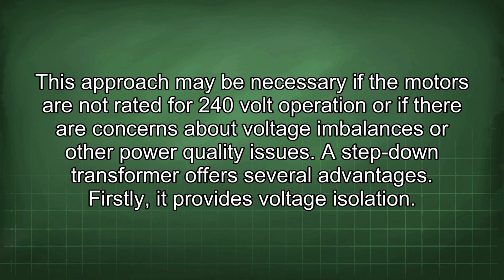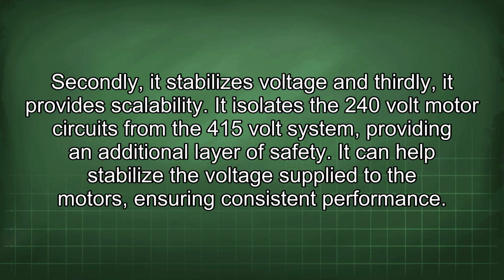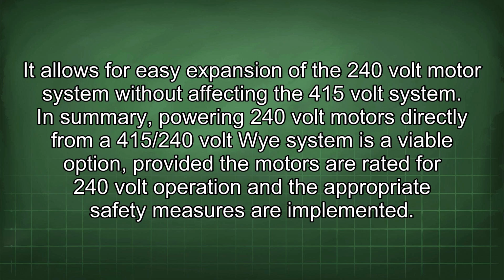A step-down transformer offers several advantages. Firstly, it provides voltage isolation. Secondly, it stabilizes voltage, and thirdly, it provides scalability. It isolates the 240-volt motor circuits from the 415-volt system, providing an additional layer of safety. It can help stabilize the voltage supplied to the motors, ensuring consistent performance. It allows for easy expansion of the 240-volt motor system without affecting the 415-volt system.